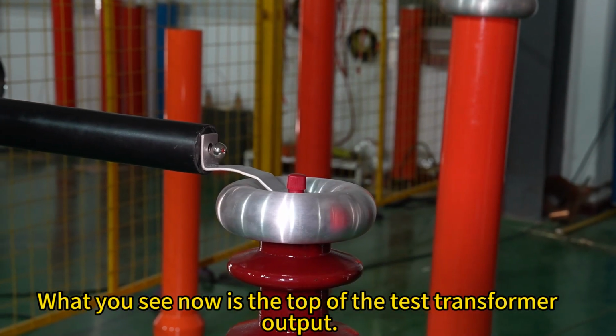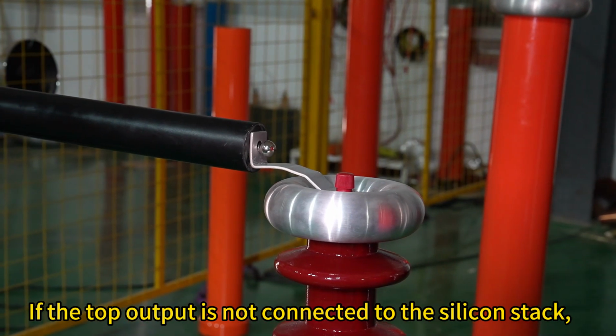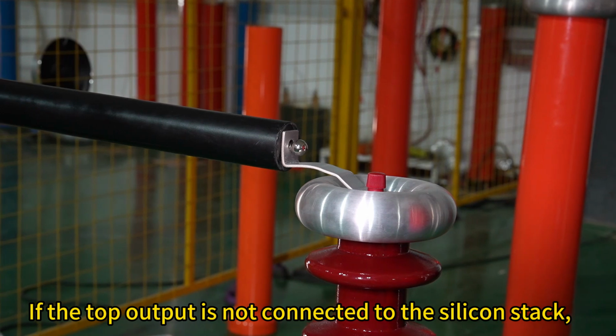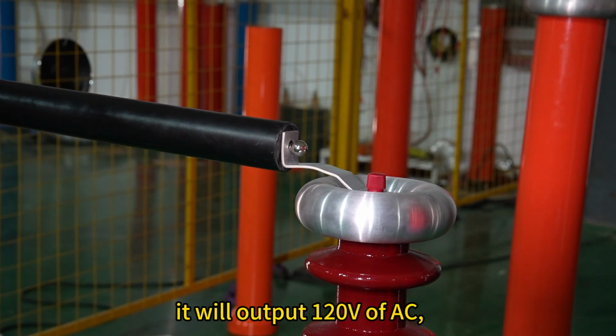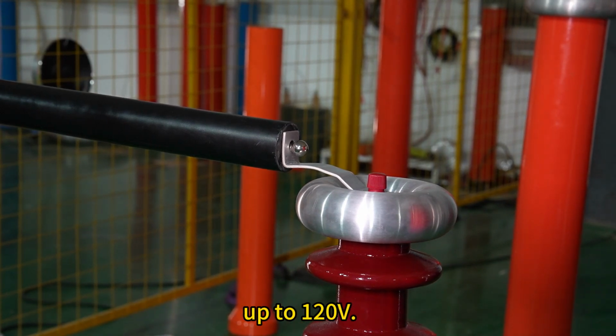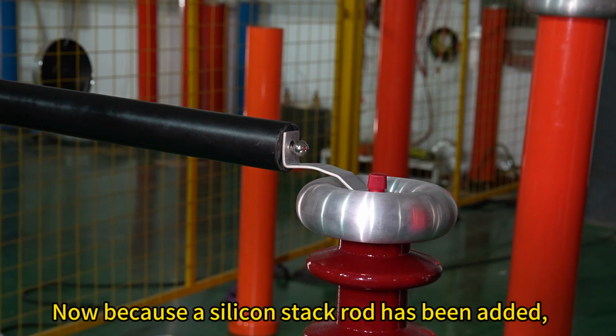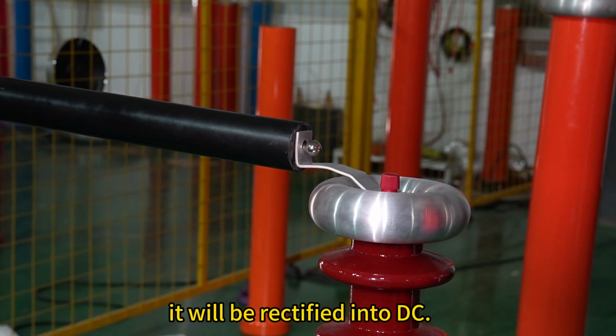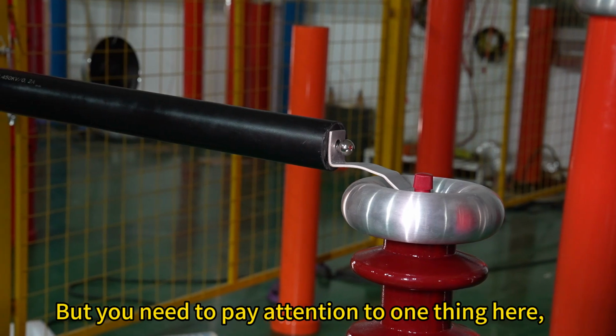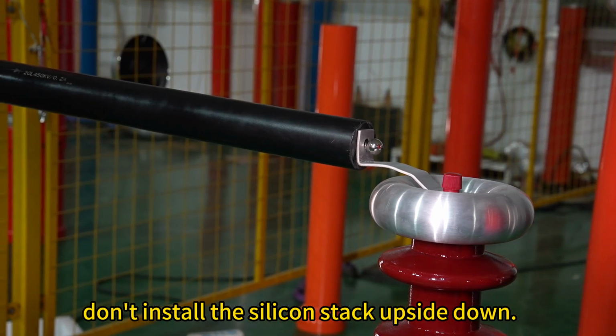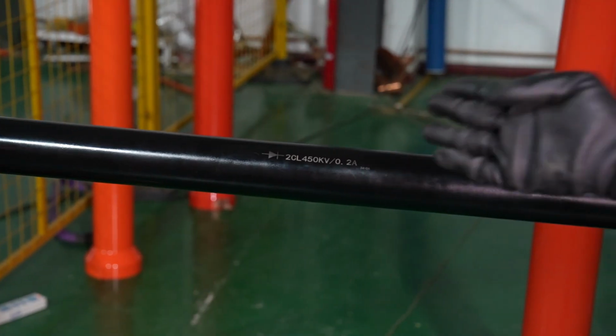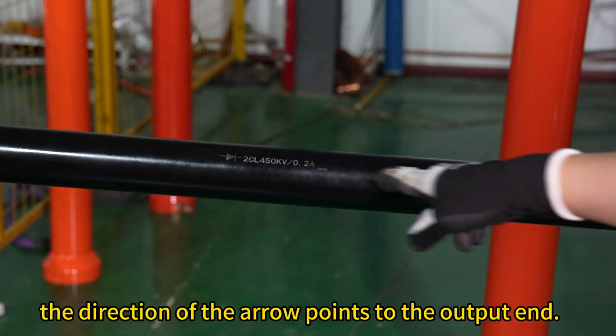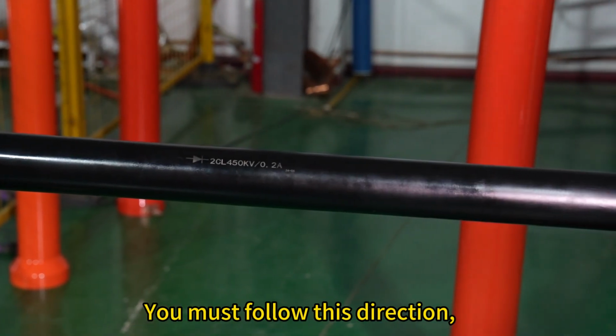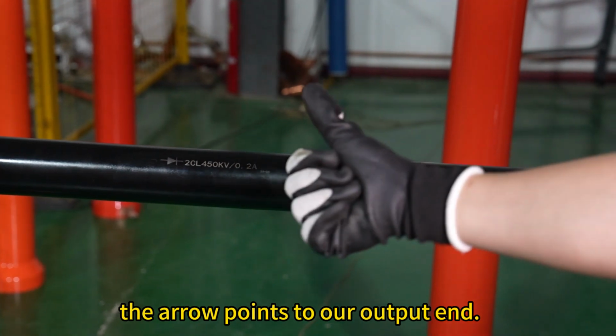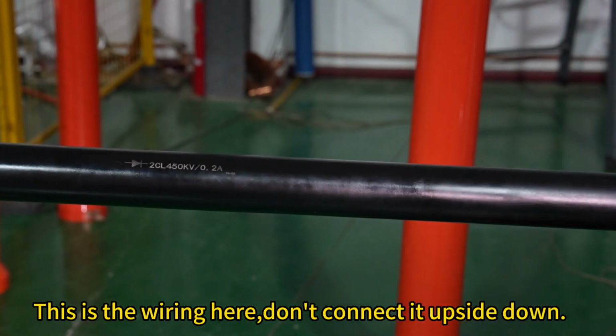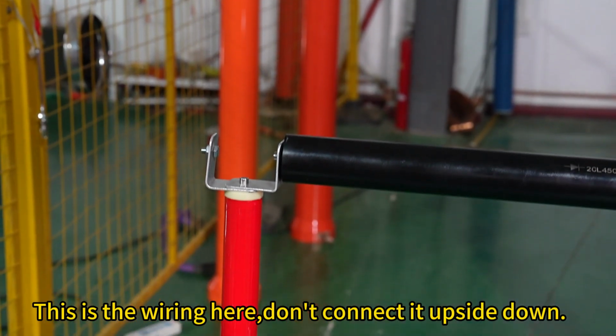What you see now is the top of the test transformer output. If the top output is not connected to the silicon stack, it will output AC, up to 120 volts. Now because a silicon stack rod has been added, it will be rectified into DC, but you need to pay attention to one thing here: don't install the silicon stack upside down. You can see this indicator, the arrow points to the output end. You must follow this direction, the arrow points to our output end. This is the wiring here, don't connect it upside down.